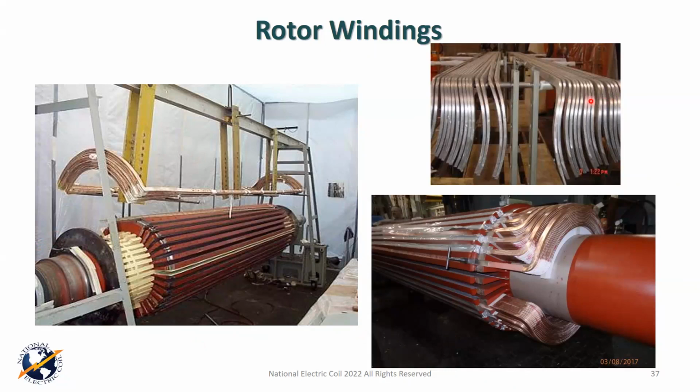Now, in this case, they're going to braze these C pieces, they call them, or half coils, in as they wind it into this machine, and they're down to the last 2 coils, it looks like. And as we look at it, here's our copper conductor going down the slot. All right, these slots are finished, and just as an FME precaution, our guys take and put tape over top of it so no little slivers of dust, dirt, or copper can get in there. And that's in there. Finishing up this one, they got this one. We'll replace that and put one here as well.